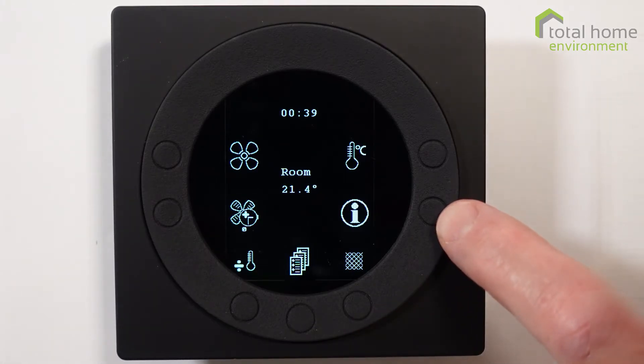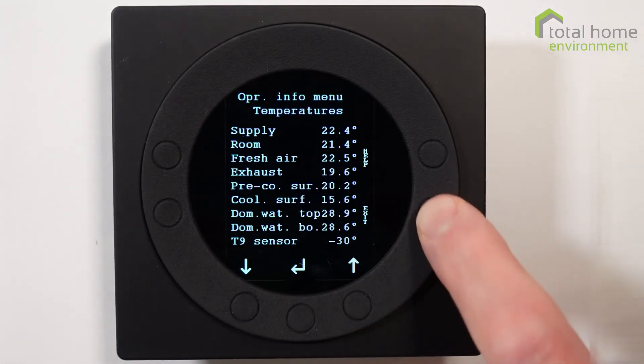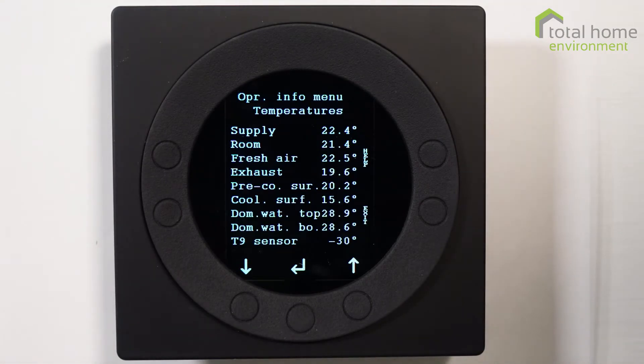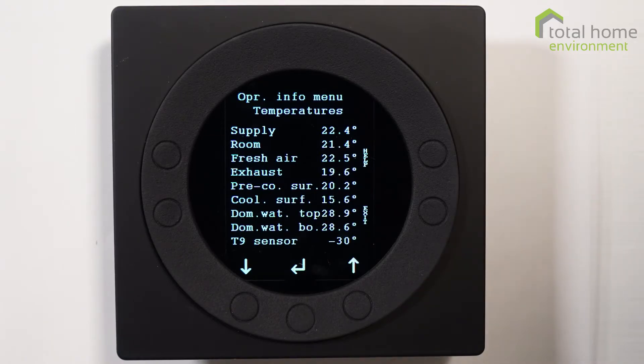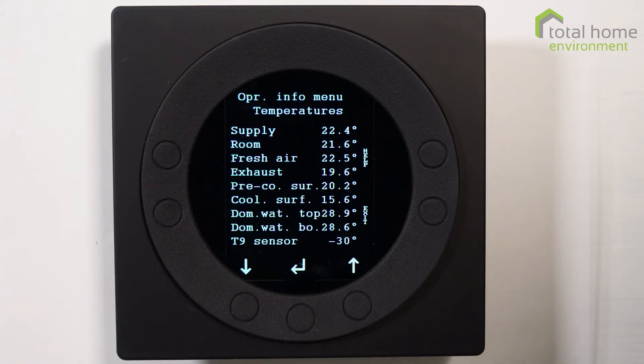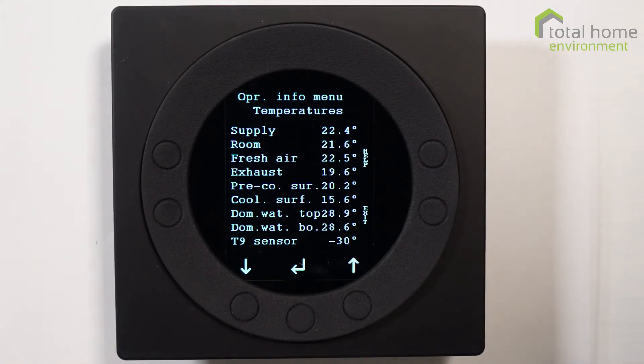The next one round is an information button. We can access that and it will tell us what our supply temperature is — supply being from the machine into your reception rooms. Room temperature is the temperature here at the controller. Fresh air temperature is the outside air temperature. Exhaust is the temperature we're exhausting from the building. The pre-cooling surface temperature is after the heat exchanger but before the evaporator coil, which is where the cooling surface is.